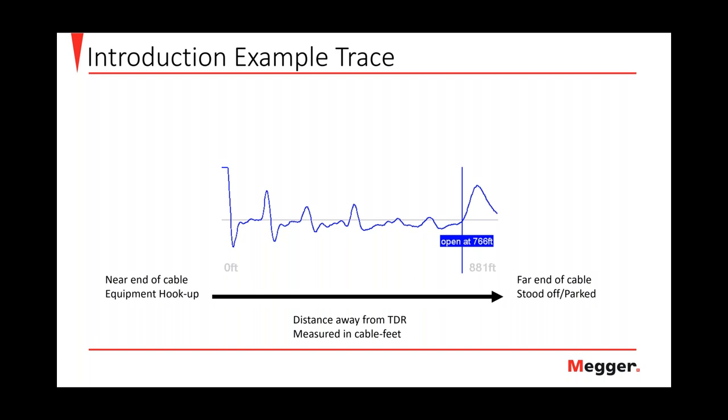On the left edge, this is the near end of the cable. So this is where our test set is hooked up. At the right end, we're going to see hopefully the end of the cable where it's either stood off or parked. And then this is the distance measured in cable feet from that TDR to the end of the conductor.